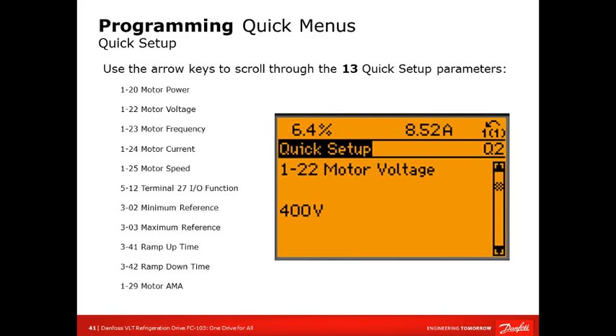Here's the quick menu setup again. It's really the basic stuff for parameter setup, just to get the motor turning. I think that's all of them there, but again, it's just a quick setup. You're going to set up your motor nameplate data into the VFD, your minimum speed and maximum speed reference, and then ramp up, ramp down.